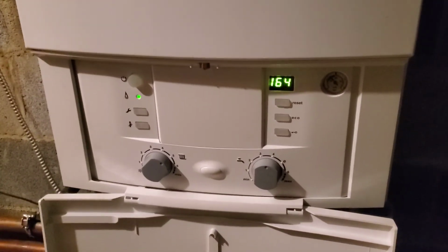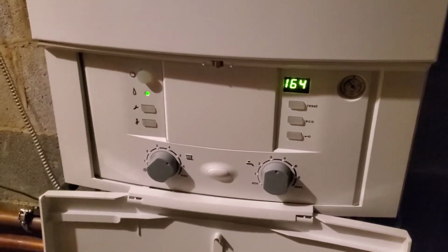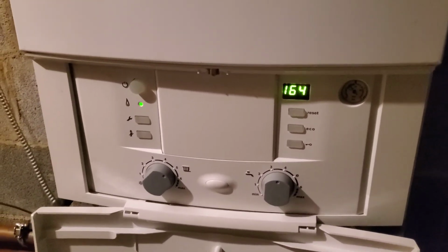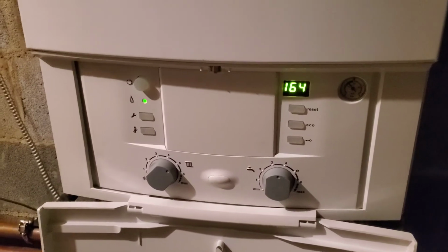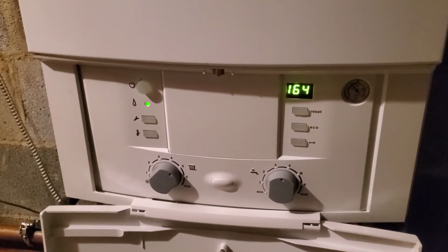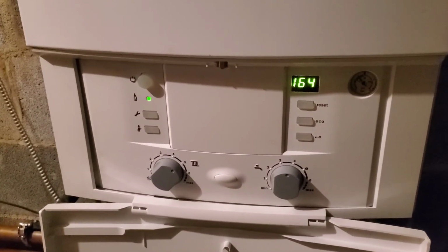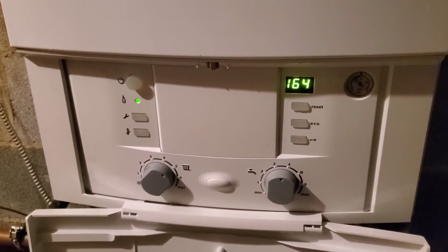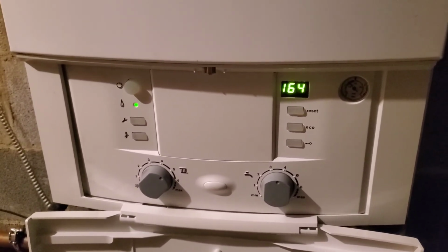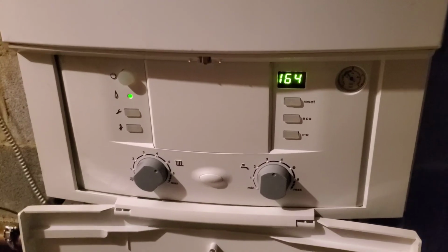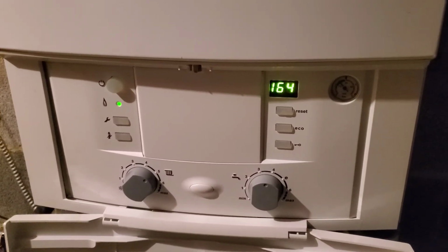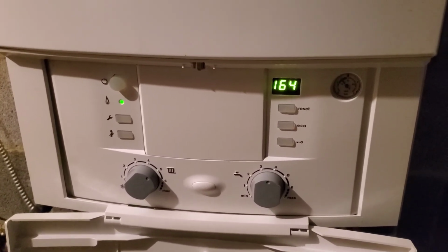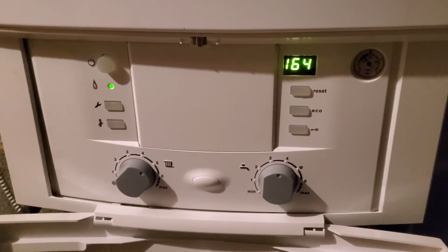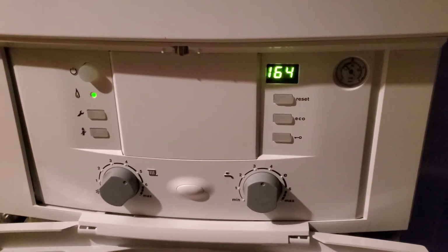This is a big house. I'm not sure what the water temperature in this boiler is supposed to be—around 180 is what I like to see. But because the boiler's been off for several days and it's cold, and there's a lot of cold water in the system, and the rooms themselves are cold, we're just going to not go any further right now. It's leveled off at 164 degrees, so it is heating.